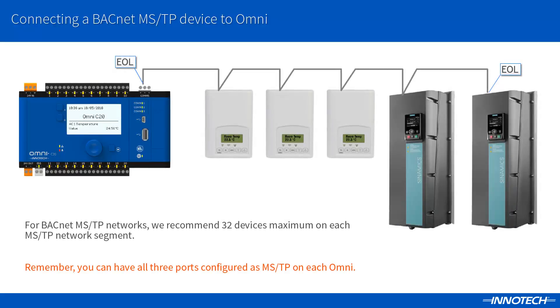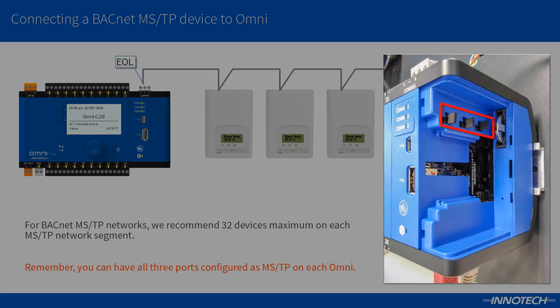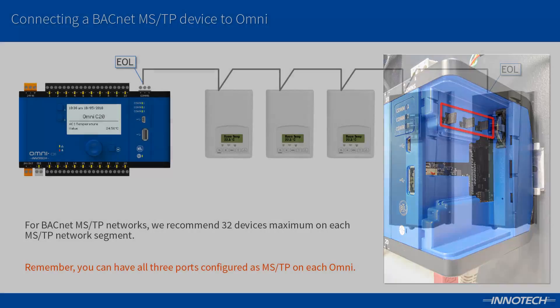The MSTP network needs to be correctly installed and terminated. This includes the end of line resistors and daisy chain topology with no more than 32 devices. This can depend on the manufacturer and could be less, so ensure that you check the documentation for more information on device capacities. Each Omni has end of line jumpers that can be set for the start of the MSTP network segment. By default these are set to off.